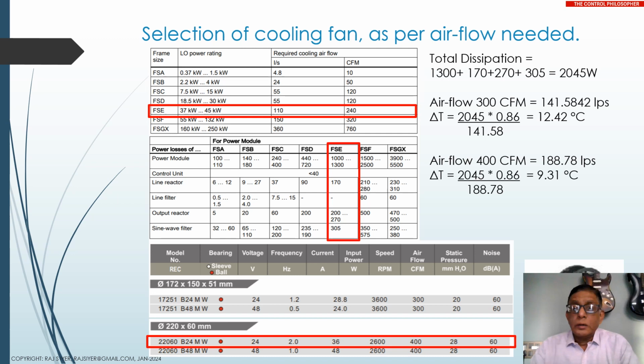Okay, in the last slide, we discussed how to mount the VFDs and calculate the dissipation, and we also came to a formula which tells us how many liters per second are required for cooling the cabinet's insides for a given increase in temperature over the ambient temperature. Usually this increase in temperature should not be more than 6 or 8 degrees. It is never to be allowed to cross some 50 odd degrees, never 60 degrees at all.